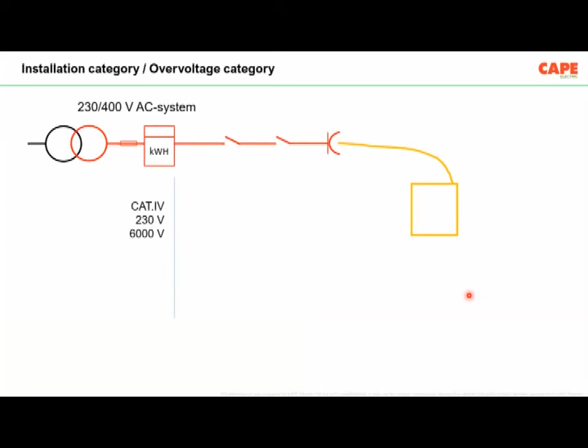You cannot even have basic safety - your building will catch fire. If you have so many earth pits all around, your building will catch fire during a fault. When we select electrical appliances for distribution in a building, at the point of commencement of supply, all electrical apparatus must be of category 4 - meaning a 230 volt item must withstand a 6 kV voltage impulse.